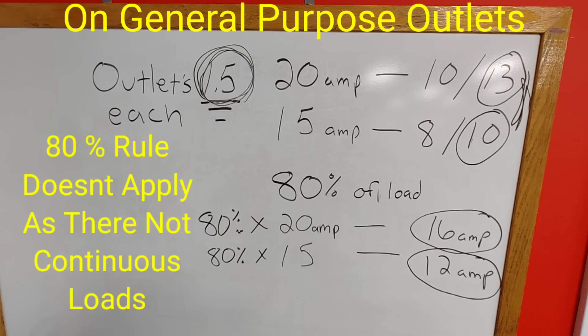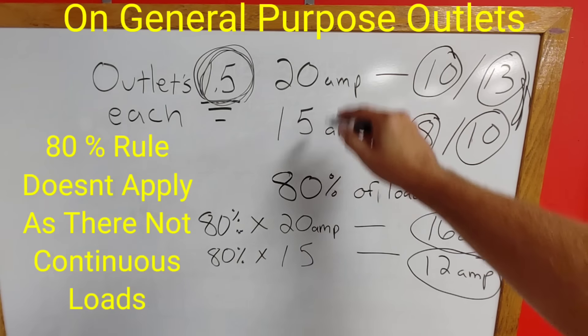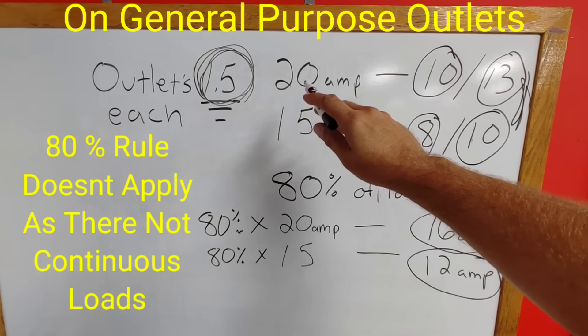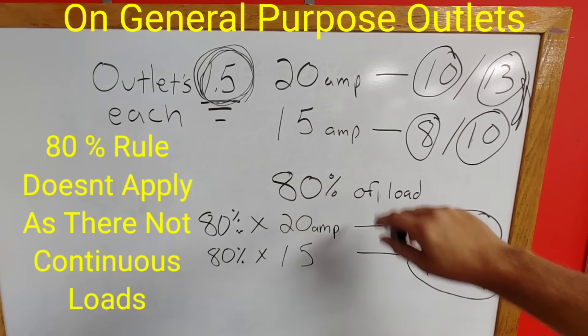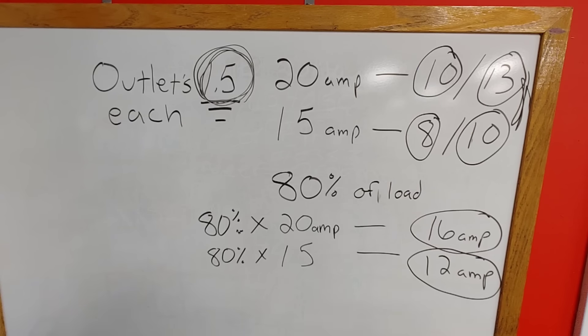And if you use that thought of logic when trying to calculate out how many outlets you can put on a circuit, that's going to take you to 10 outlets or 8 outlets depending on what amperage circuit you're using. So if it's a 20 amp breaker it'll be 10 outlets. If it's a 15 amp breaker it's 8 outlets. But again, technically there really is no wrong answer.